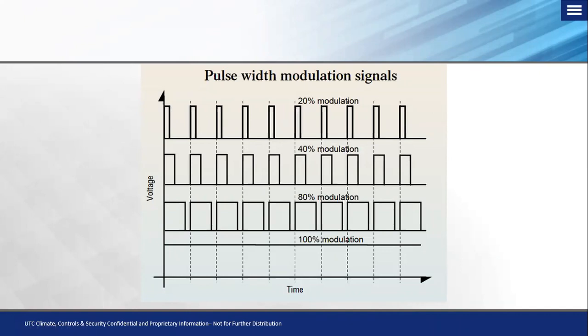Now, when you hear the term pulse width modulation, which has become popular with many household appliances and air conditioners just because of the energy efficiency that's associated with it, what that term actually means is this: the pulse would be the amount of signal sent to the individual terminal, whether it be W, V, or U. The width, in this case, would reference this chart, or the amount of pulse that's actually being sent, whether it's a 20% pulse, a 40% pulse, an 80% pulse, or full modulation. And then of course the modulation would be the frequency that the algorithm is going to pulse that off onto the switches to control the speed of the compressor.